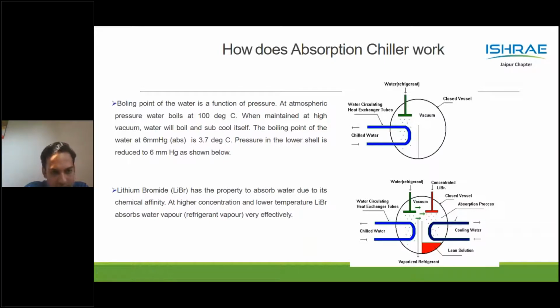Why is it boiling? As we discussed, the boiling side inside the shell is at 3.7 degrees, and as it comes in contact with the 12-degree tube, it boils off. As it boils, it converts into vapor, and this increases the pressure inside the shell.